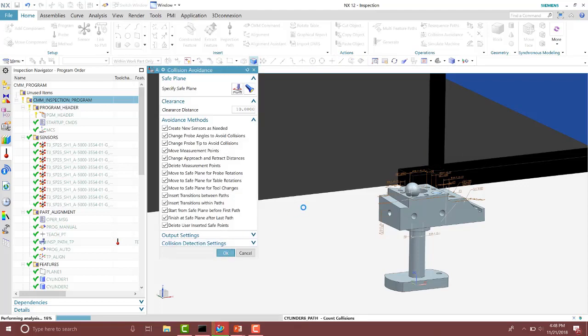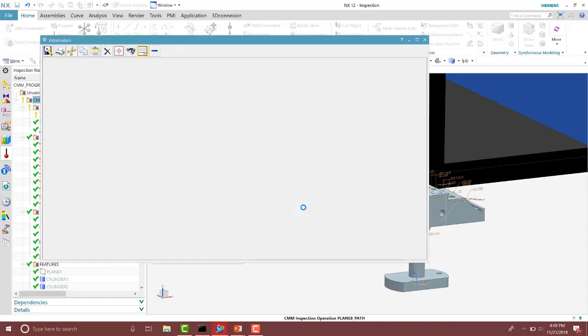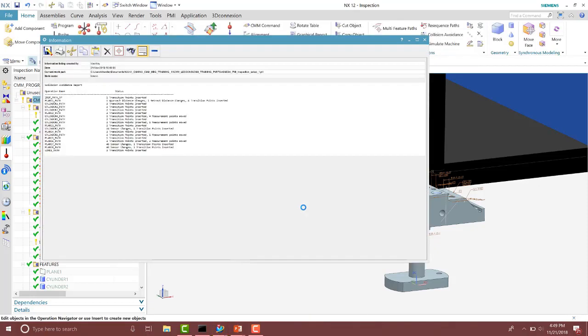As you press OK it will then optimize those paths. Notice at the bottom there it's finding the correct probe angles. And then you'll see some points are moved and some points have been inserted. After the collision avoidance has been run, you will get a report on all of the paths.